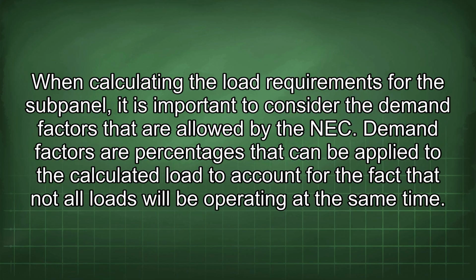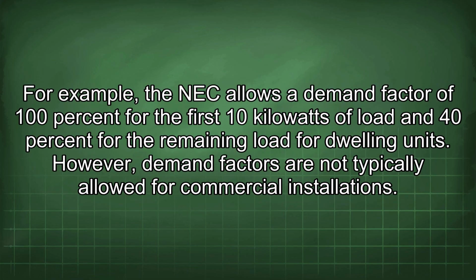When calculating the load requirements for the subpanel, it is important to consider the demand factors that are allowed by the NEC. Demand factors are percentages that can be applied to the calculated load to account for the fact that not all loads will be operating at the same time. For example, the NEC allows a demand factor of 100% for the first 10 kilowatts of load and 40% for the remaining load for dwelling units. However, demand factors are not typically allowed for commercial installations.